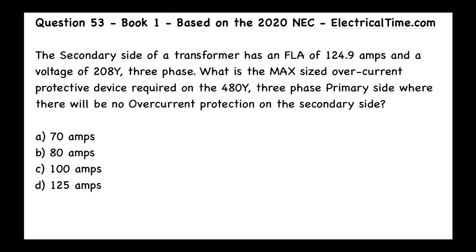This is question number 53 from book number one, based on the 2020 NEC from electricaltime.com. The secondary side of a transformer has a full load amps (FLA) of 124.9 amps and a voltage of 208V Y three-phase. What is the max sized overcurrent protective device required on the 480V Y three-phase primary side where there will be no overcurrent protection on the secondary side? Choices are 70A, 80A, 100A, and 125A.